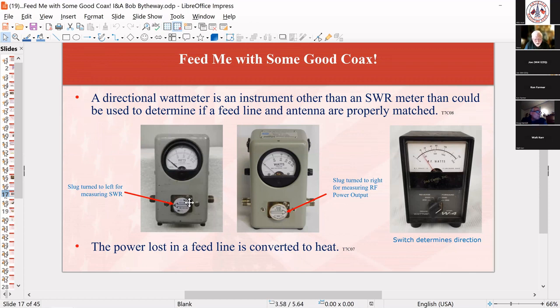Then you use a lookup table that tells you what the SWR is. So turn the slug to the right to measure the RF output, turn it to the left to measure the reflected power, then look up the SWR. Generically you're measuring SWR, but to the left you're actually measuring reflected power. A directional watt meter is the one — that's C7, C8.